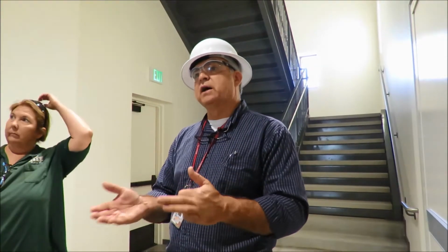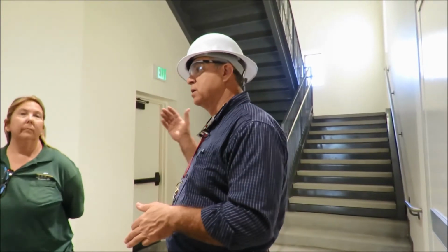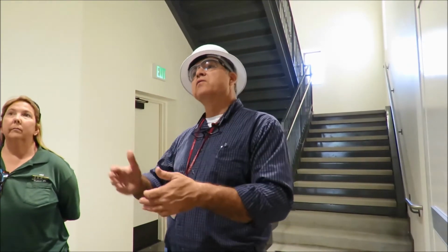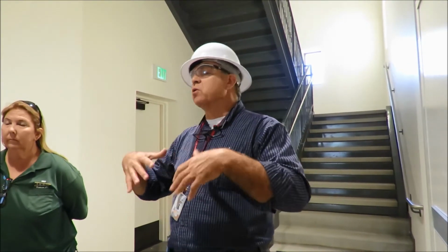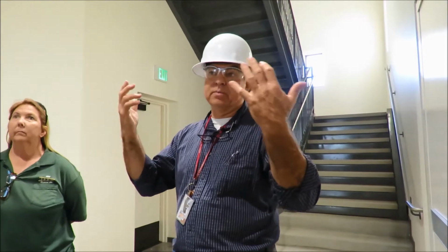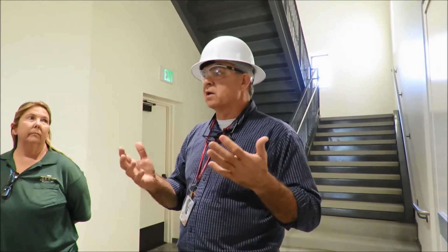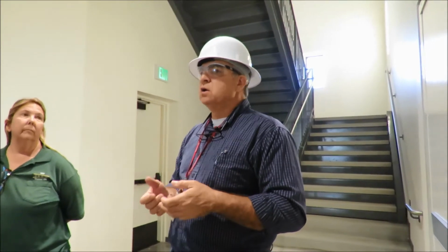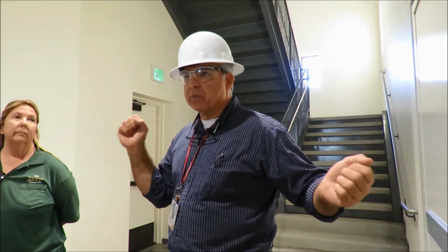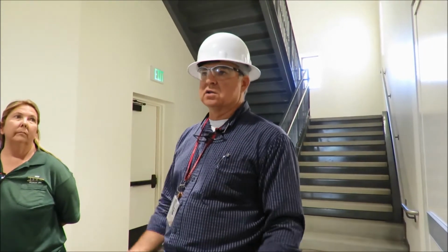Well, the smoke sensor is not in the room. It's in the ductwork further down. So the room could be full and nothing's really happened yet. The people are still trying to figure out what to do. So really what we need to educate folks is you open the door and you pull the pull alarm, and that now sets everything into sequence, including the HVAC system.